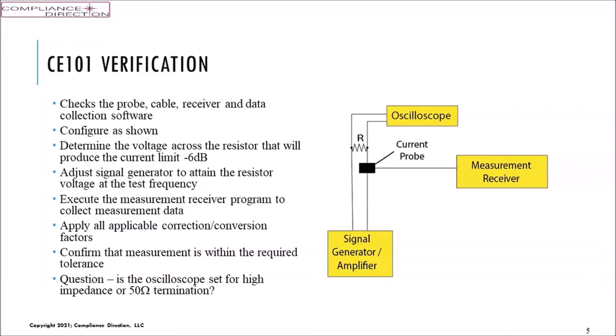I throw a question in here that we'd like to see. Is the oscilloscope set for high impedance or 50 ohm termination? Well, if I do a 50 ohm termination, the resistor is in parallel with the oscilloscope 50. So if I'd selected a 25 ohm resistor and a 50 ohm oscilloscope, we have about 16, 17 ohms of resistance. And so the R value has changed. So we want the oscilloscope not to affect the measurement. That is a measurement instrument that should not have the effects. We need to select 50 ohms if our measurement device demands 50 ohms for its calibration, like the current probe output going to the receiver is a 50 ohm termination, and the correction factors have that necessity to make it 50.